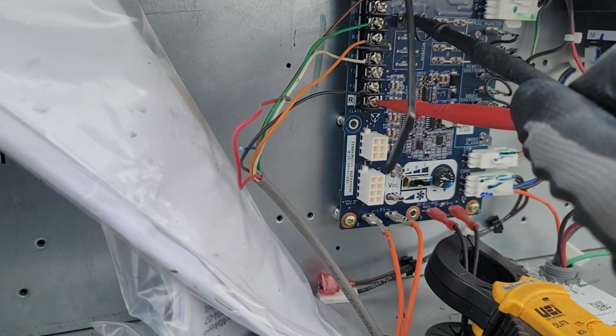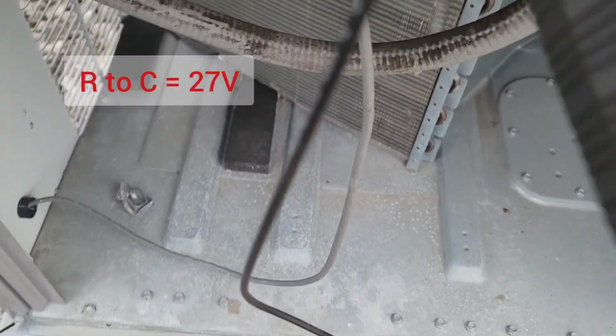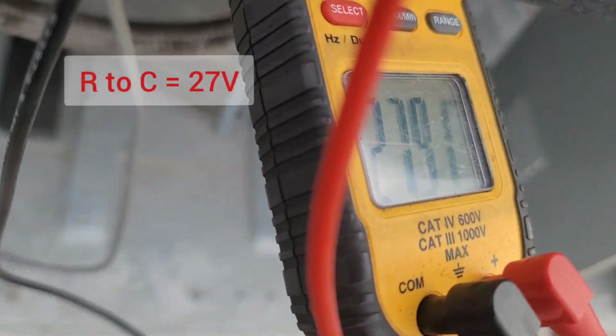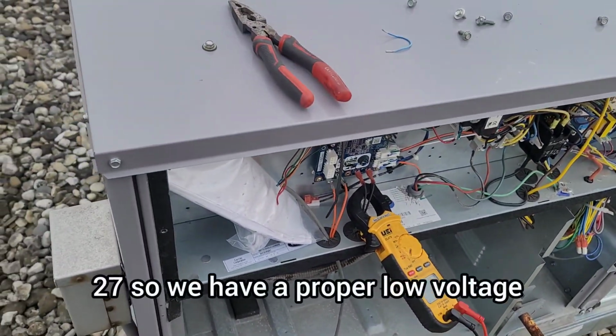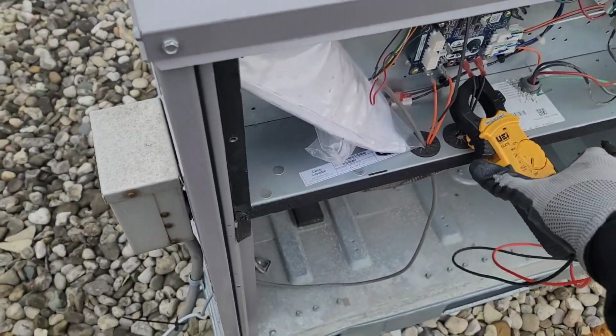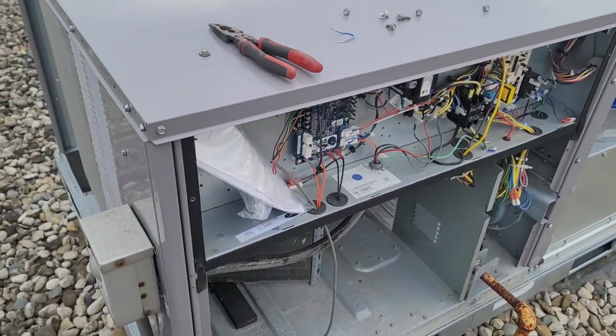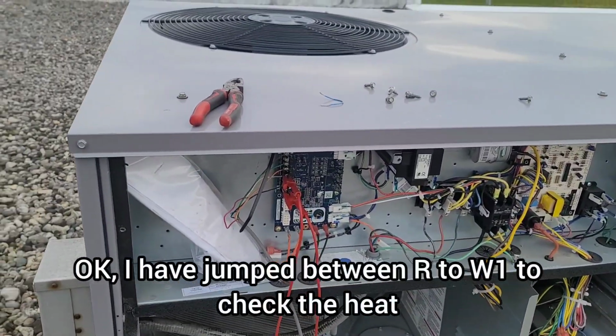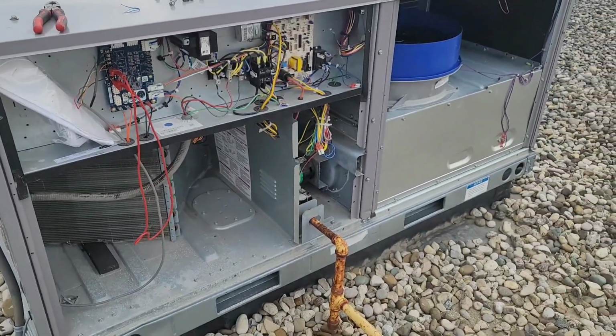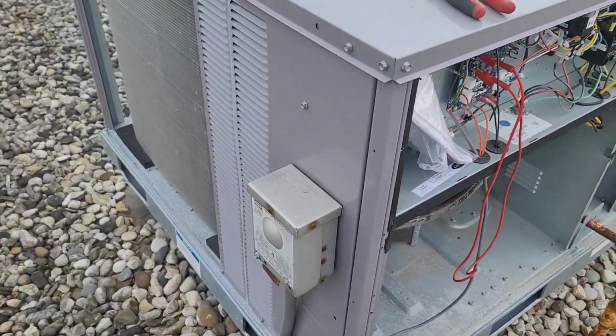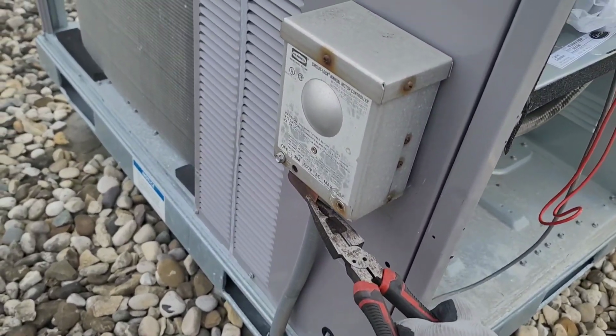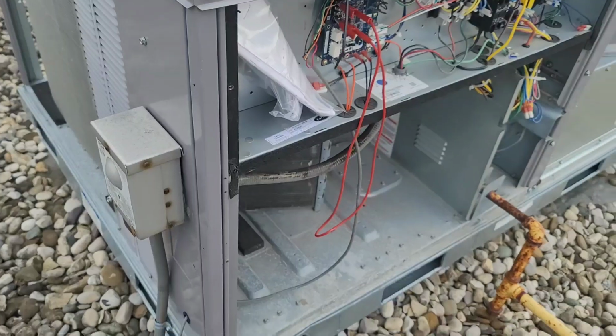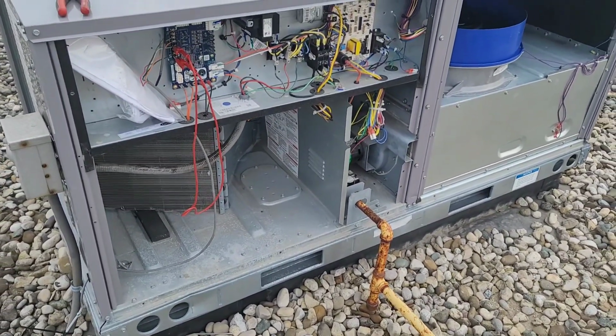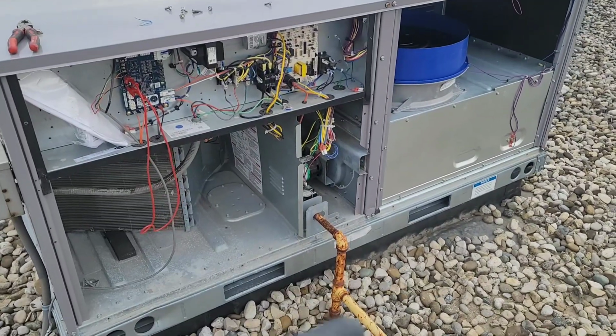Let's check our low voltage. Between R to C, we have 27. Sorry, yeah, 27. So we have a proper low voltage and high voltage. Okay, I have jumped between R to W1 to check the heat, and let's turn on very carefully. Venter motor, as I said, it was okay, so the unit fired up properly.